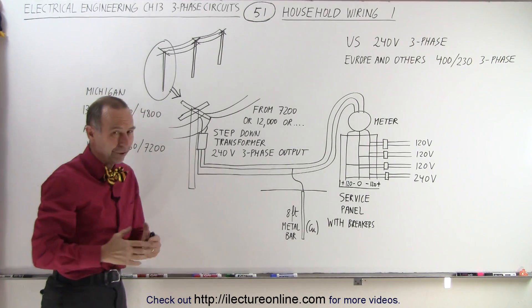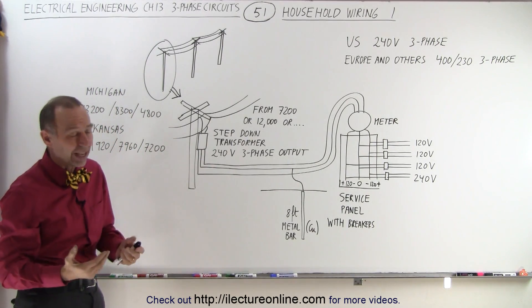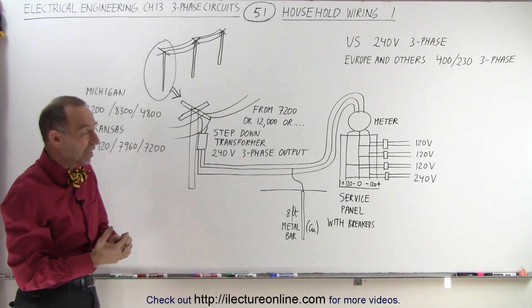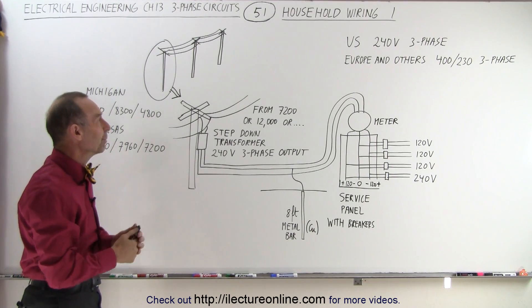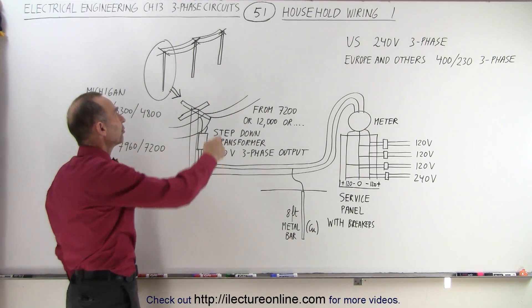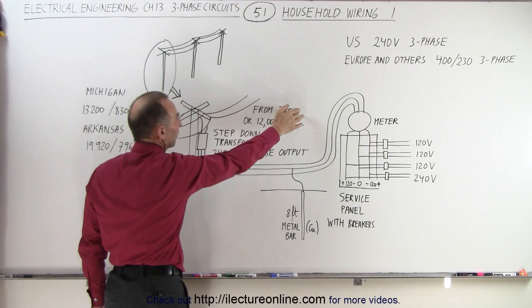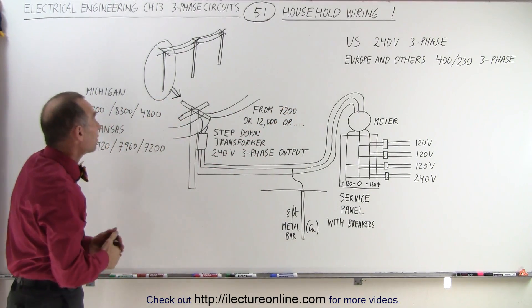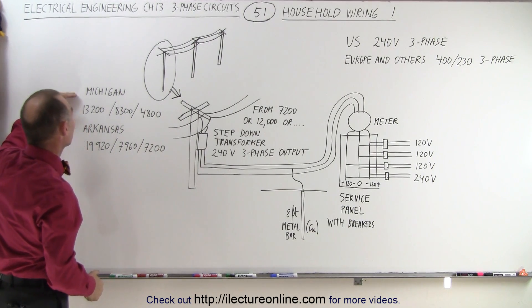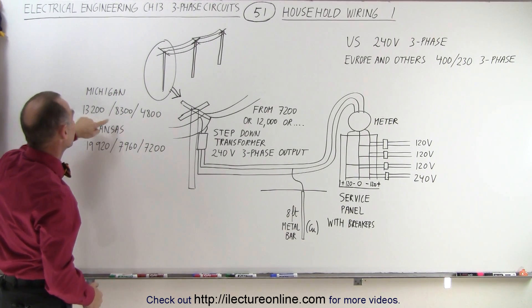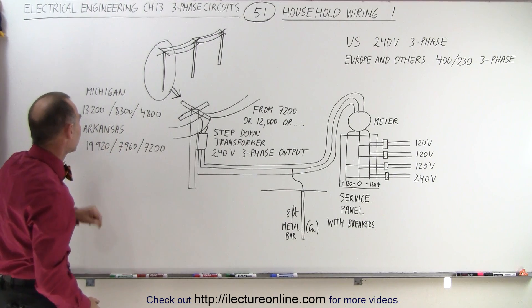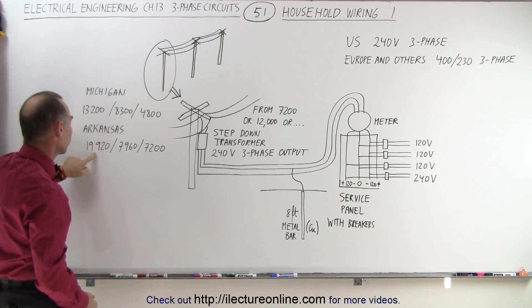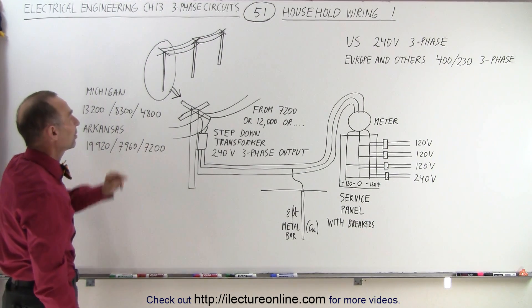The voltage on the lines outside varies quite a bit from state to state and from region to region. There's not an absolute uniformity to that. Typically the voltage on the lines outside could be as much as 7,200 volts or even 12,000 volts or even higher. In Michigan the voltage can be 13,200, 8,300, or 4,800. In Arkansas it can be almost 20,000, 7,960, or 7,200.